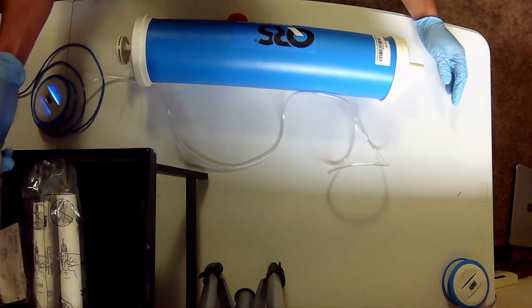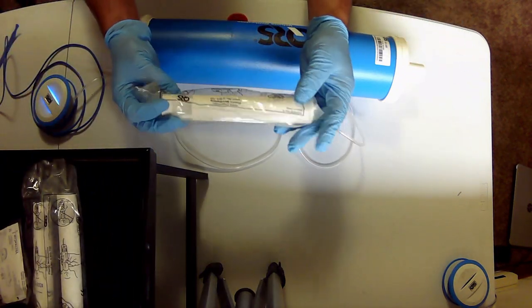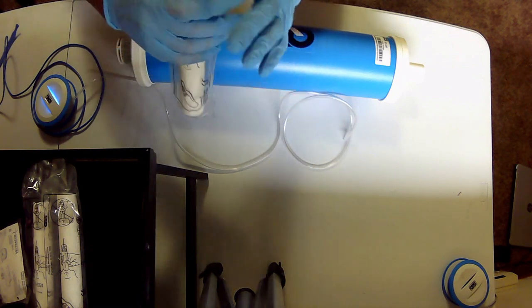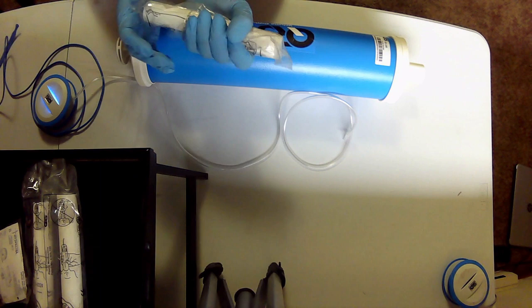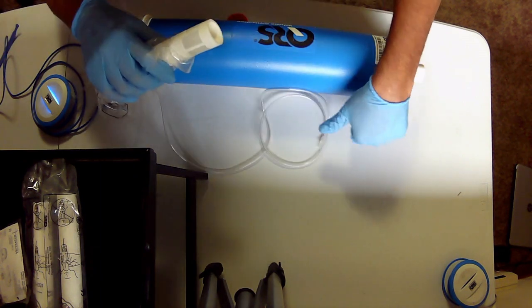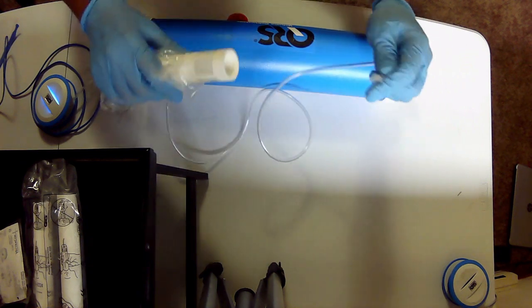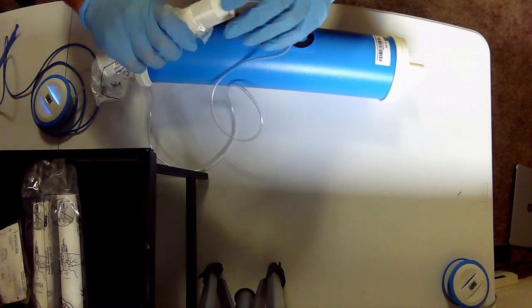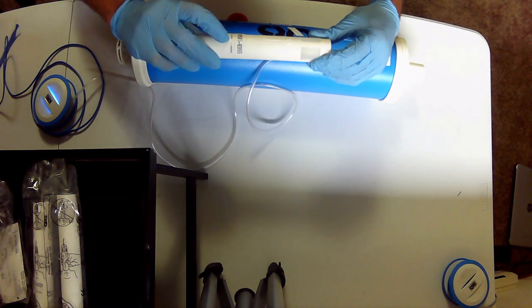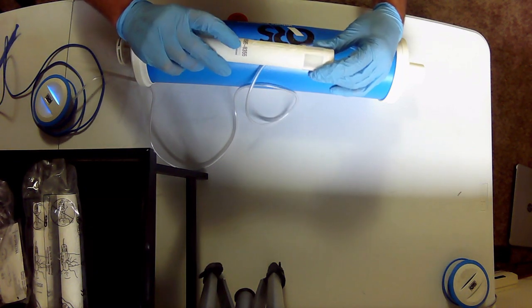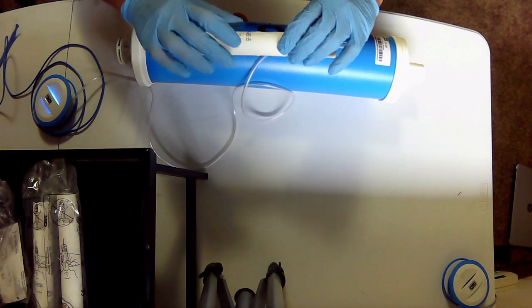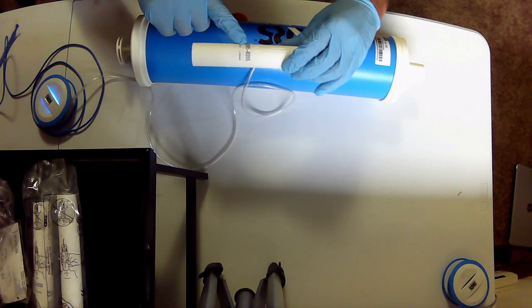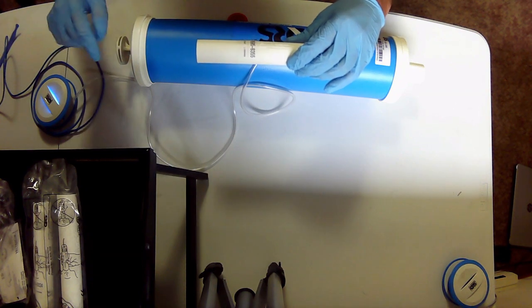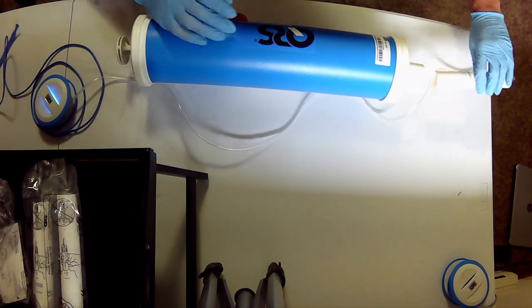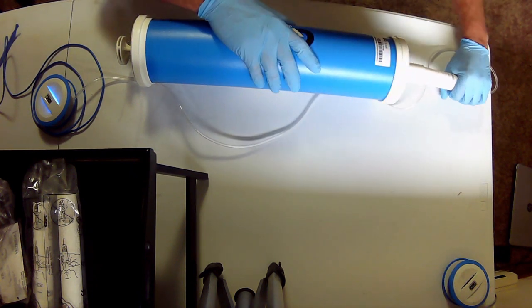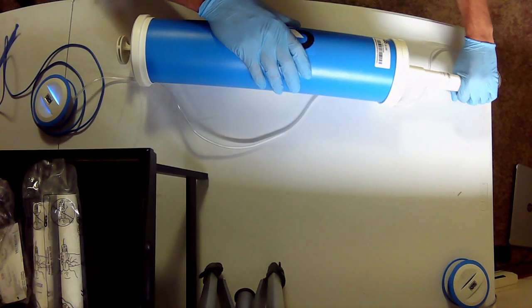And next we'll need the mouthpiece, QRS mouthpiece. And here's the end that has the fitment on it. We're going to go ahead and open that up. Connect the pressure tube to the mouthpiece. And you note here that we have the calibration number. This is actually a calibration number because all of our mouthpieces are pre-calibrated from the factory. So when we put in this number, we're actually calibrating the device for this specific mouthpiece. And I'm going to go ahead and insert that into the end of the calibration syringe.